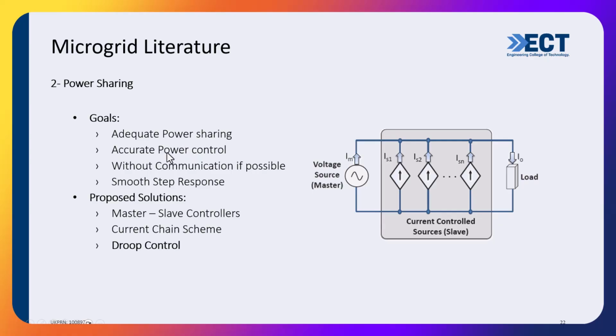Okay, accurate power sharing, so if I want to push 1 kilowatt, for example, I push exactly 1 kilowatt, not more, not less. And we want to try to do that without communication. For example, we don't need communication between the different inverters, and we want a very smooth step response, so we don't want oscillation and resonance. How to do that? We have, for example, master-slave controllers where we communicate with each other. But because we don't want communication, we use something called droop control.